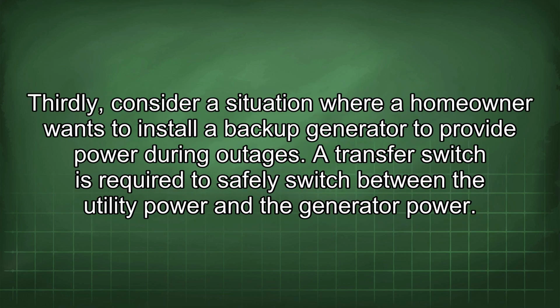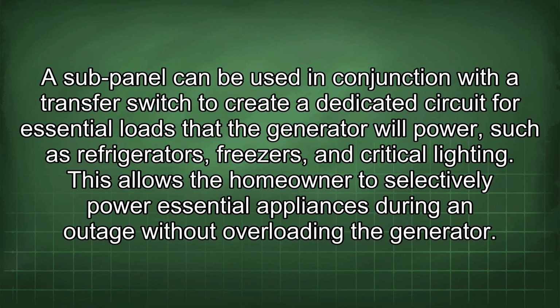Thirdly, consider a situation where a homeowner wants to install a backup generator to provide power during outages. A transfer switch is required to safely switch between the utility power and the generator power. A sub-panel can be used in conjunction with the transfer switch to create a dedicated circuit for essential loads that the generator will power, such as refrigerators, freezers, and critical lighting. This allows the homeowner to selectively power essential appliances during an outage without overloading the generator.